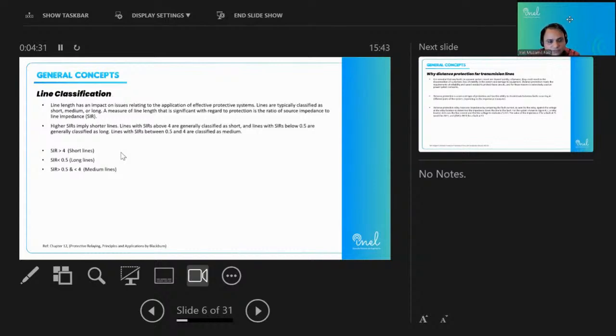Now, there is another classification of lines, which is on the basis of source impedance ratio. It is more concerned with the location of the relay and the fault level available at the station where we are going to connect our relay for protecting a transmission line. Generally, there is a source to line impedance ratio, meaning source impedance to line impedance ratio. If it is greater than 4, then it is a short transmission line. Let me show you.